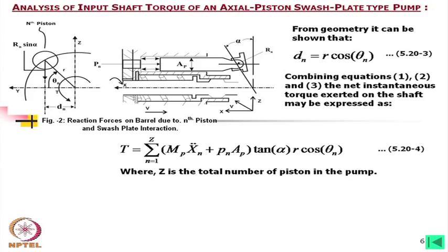Say then we can separately calculate these for 1 megapascal and 10 megapascals, or else we can take the pressure difference equal to 9 megapascal. So, when the particular chamber is on the suction side, this pressure is 0. So, this part will not come, automatically this will become 0. However, this part will be there, but this again depends on the acceleration and decelerations, sometimes it will help and sometimes this will reduce the torque and sometimes it will increase the torque.